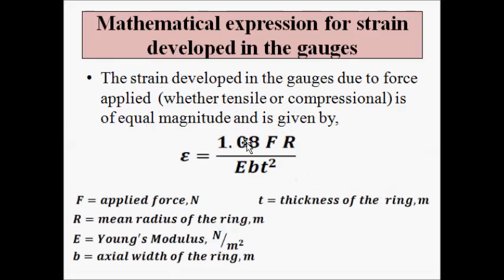The interesting thing about the mathematical expression for the strain induced in the four strain gauges is that whether the strain is tensile or compressional, the magnitude of both strains are equal. The expression is: ε = 1.08 × F × R / (E × b × t²), where F is the applied force in newtons, R is the mean radius of the ring, E is Young's modulus of elasticity, b is the axial width of the ring, and t is the thickness of the ring.